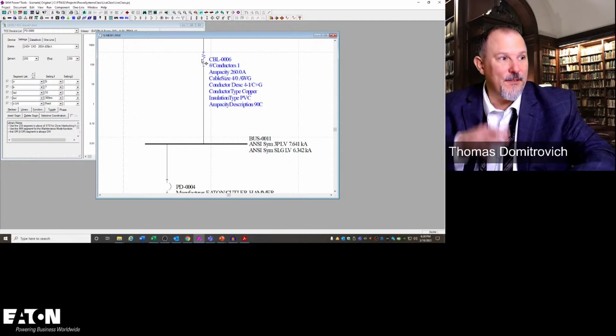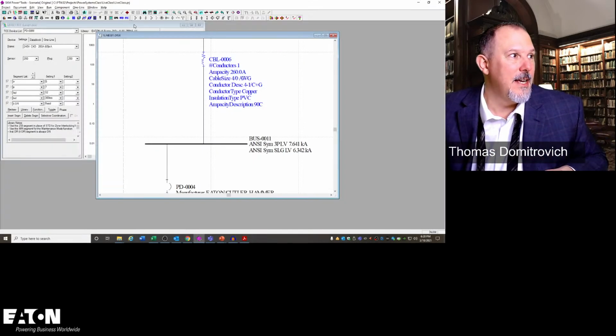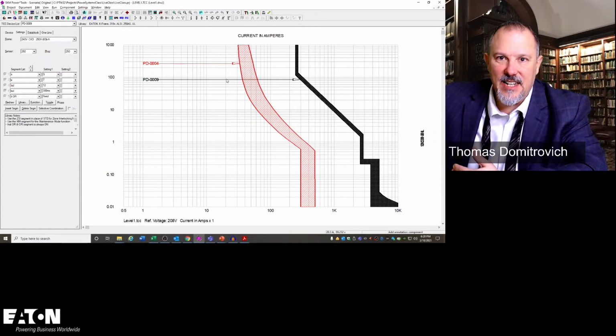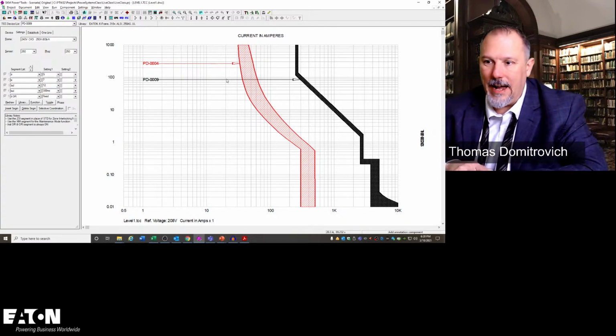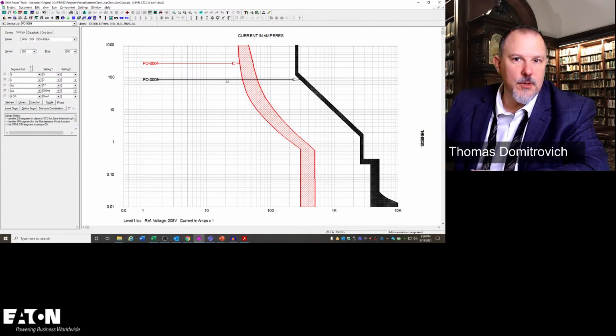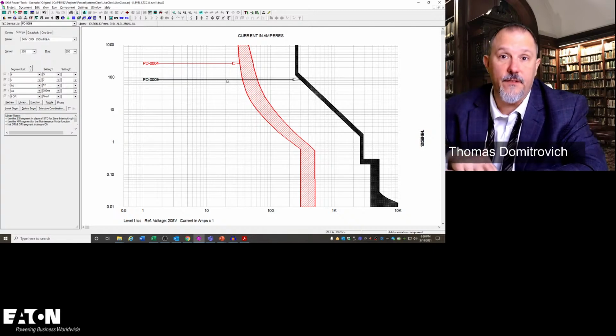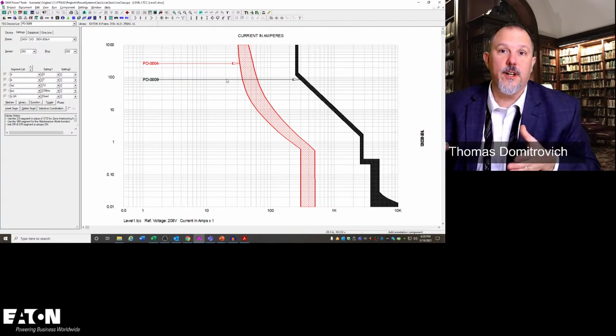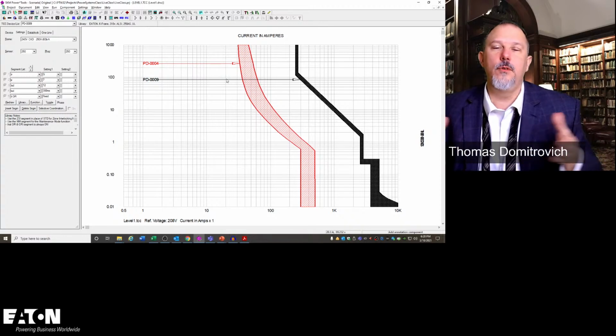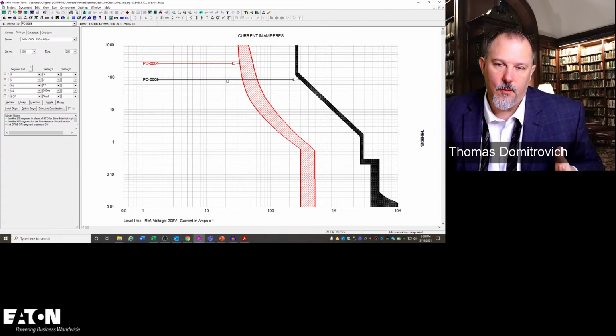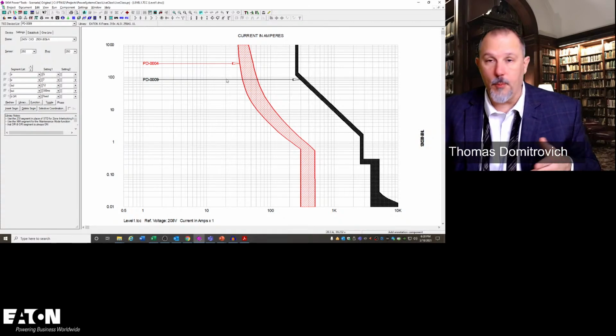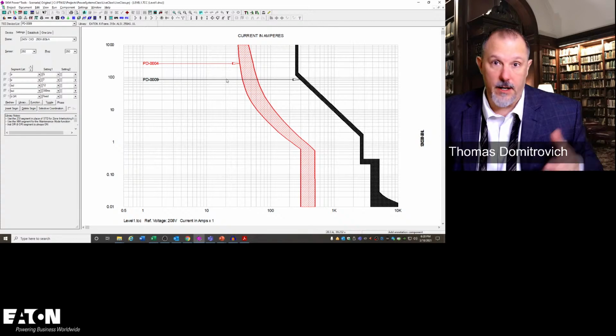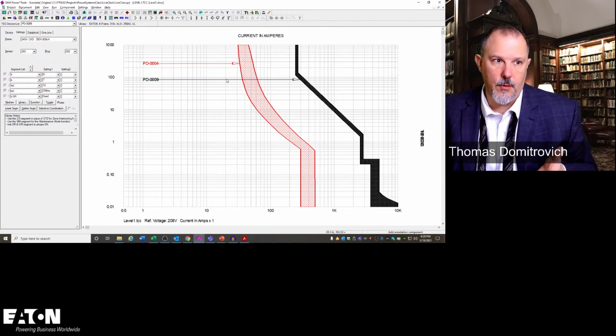Think about it. There's different ways to solve this problem. I can increase the size of my upstream overcurrent protective device, or I can tell my electrician, go take a few laps around the block with your conductor and reduce the fault current. One-to-one transformers, beautiful, beautiful solution. Well, what does that do? One-to-one transformer, that adds another overcurrent device. You need to put a primary and secondary. It adds space, right? And cost just to knock fault current down. So maybe a little bit longer of a run if you can get away with it.